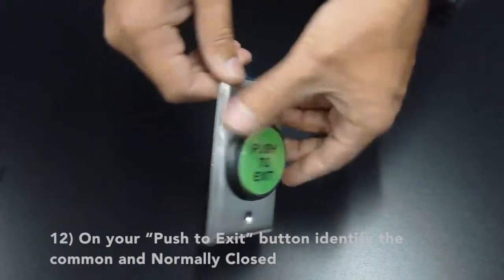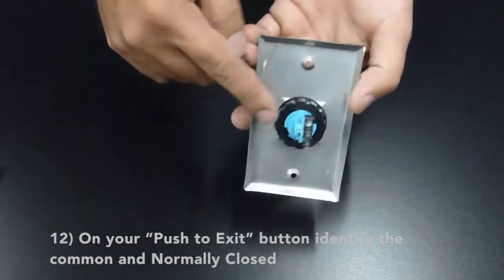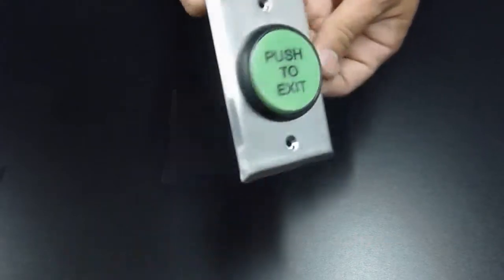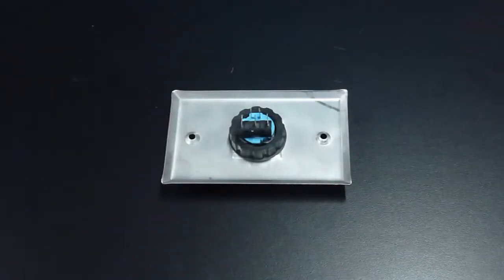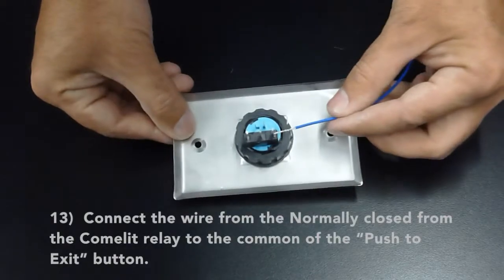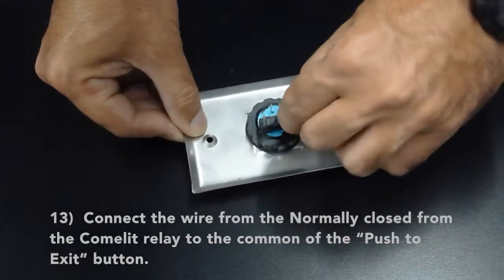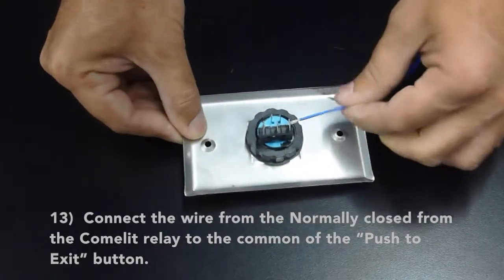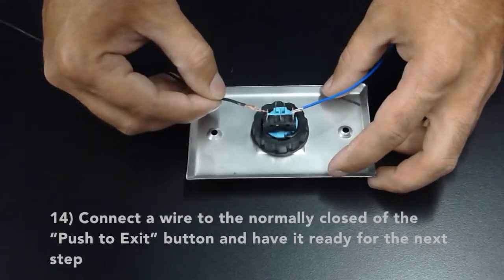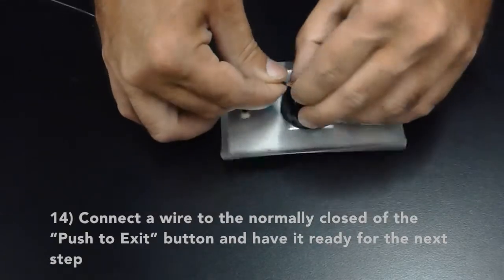Now on your push to exit button, identify the common and the normally closed. Connect the wire from the normally closed of the Comelit relay to the common of the push to exit button. Connect the wire to the normally closed of the push to exit button and have it ready for the next step.